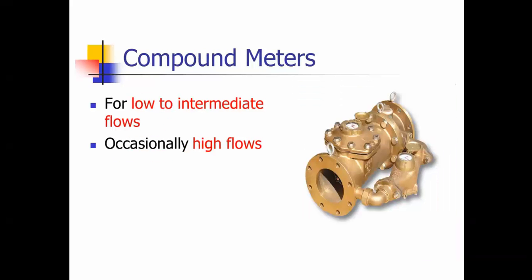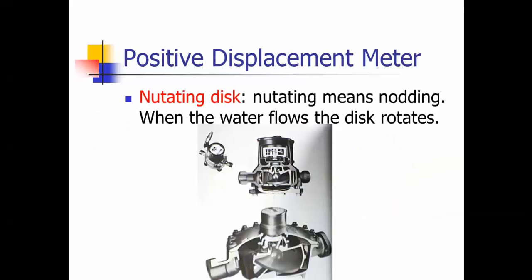Compound meters, you can see it's a main meter and a smaller meter off to the side. They're for low to intermediate flows, and occasionally they use those for high flows. Positive displacement meter, this is a nutating disc, and you can see this is the measuring chamber down in here, and you can see the disc as that rotates, it turns the totalizer.